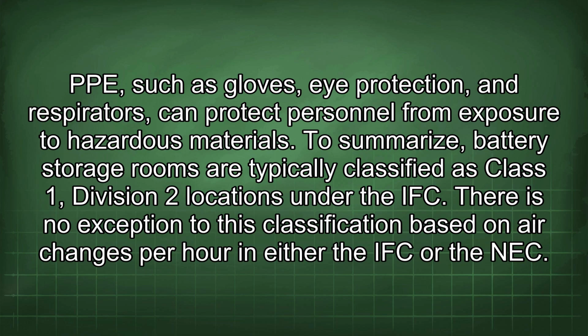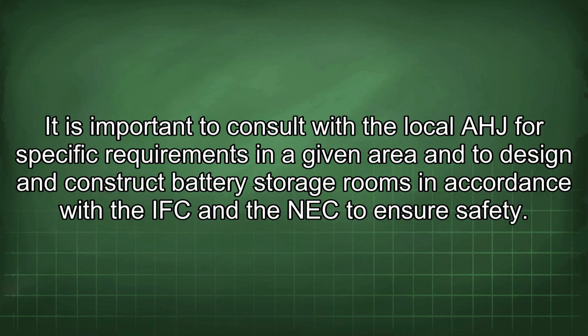To summarize, battery storage rooms are typically classified as Class 1, Division 2 locations under the IFC. There is no exception to this classification based on air changes per hour in either the IFC or the NEC. It is important to consult with the local AHJ for specific requirements in a given area and to design and construct battery storage rooms in accordance with the IFC and the NEC to ensure safety.